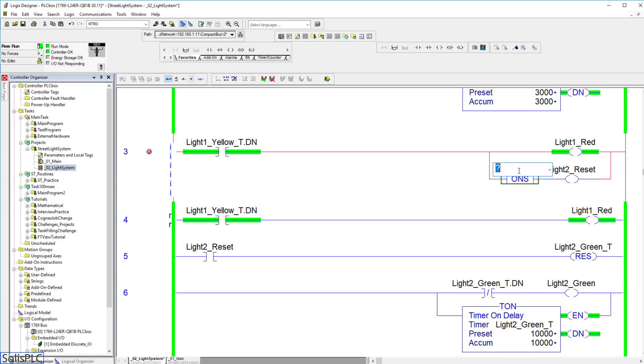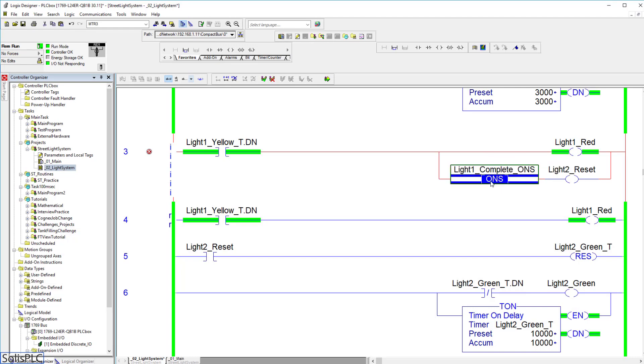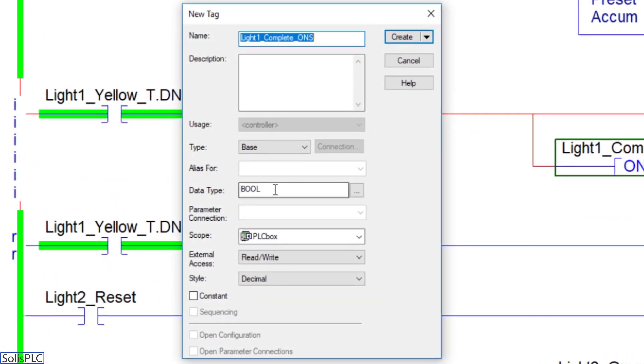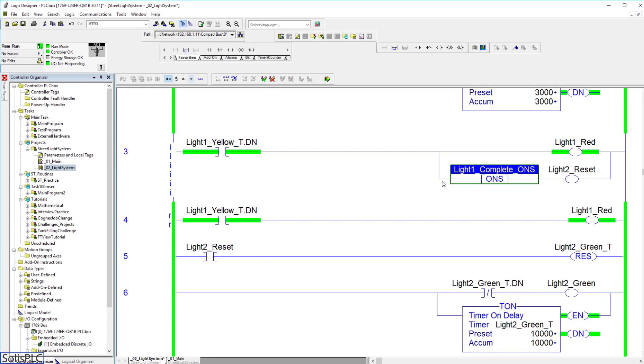Here I'm going to have to create a tag specific to that one-shot. I'll type in light1_complete_ONS. I typically like to give my one-shot instructions that specific naming convention so you know exactly what you're dealing with when looking at the tag list. We're going to have to create that, so right-click, new, light1 one-shot. It's going to be of type boolean, residing on the PLC controller. Hit create, and we should see no errors on that branch.